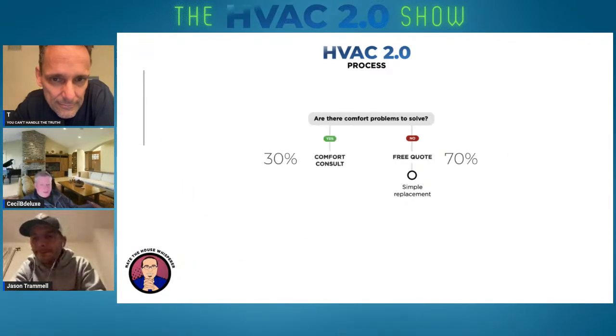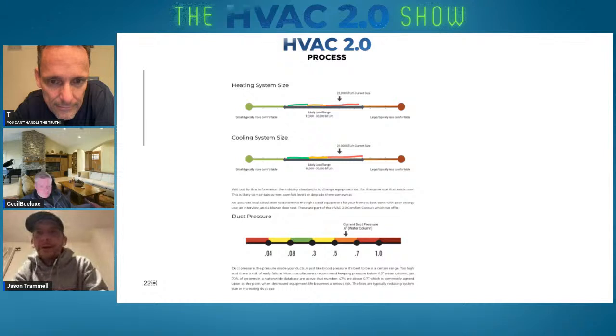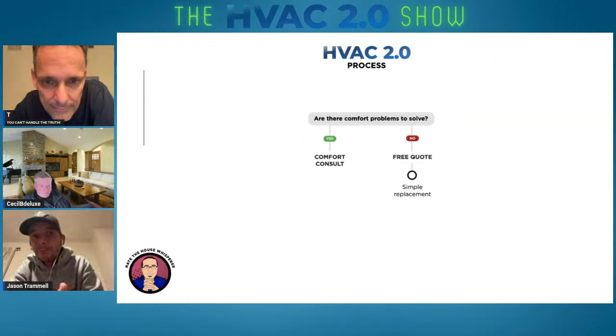So what makes it do that? Because you have to slow or speed up the airflow? No, because the coil's bigger, so it runs at a higher temperature to get the rating. So say the evaporator's 50 degrees versus a 40-degree evaporator. Well, it's not going to remove as much humidity, because at some point the dew point's going to meet the temperature of the air running across it, so it's not going to do any dehumidification. So they rated at a point where there's no latent capacity because the dew point of the coil is the same as the dew point of the air or higher. So the high efficiency coils are usually the oversized coils.